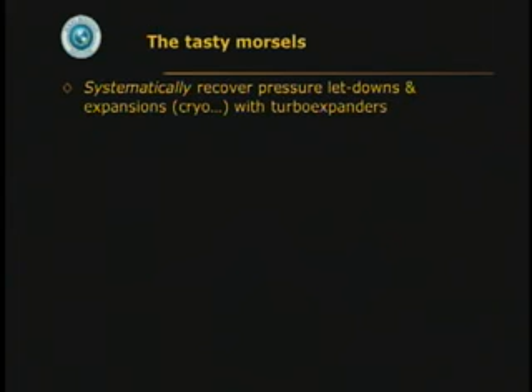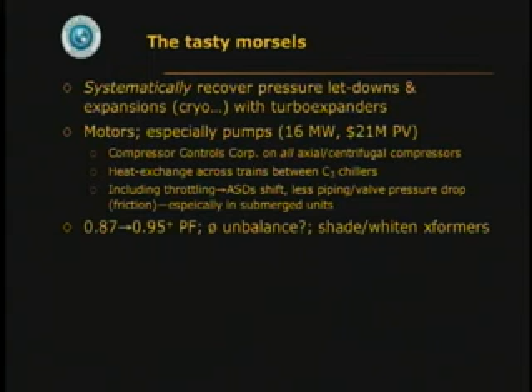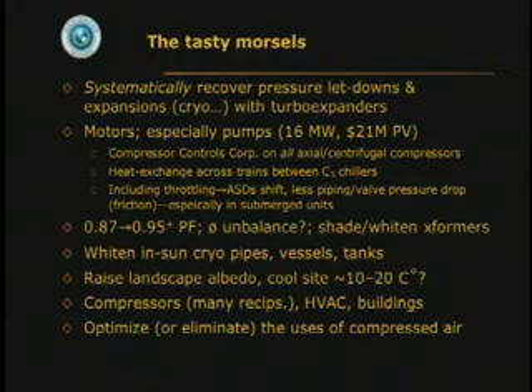Of course, there are the motor and especially pump improvements, proper controls on compressors, heat exchange between the parallel LNG train with propane chillers, shifting from throttling valves to adjustable speed drives, getting rid of frictions, and improving power factor, phase unbalance, painting the transformers white, whitening everything that's in the sun and has to be kept cold, including the landscape, improving compressors, mechanical systems, buildings, and getting rid of compressed air or at least optimizing its use.